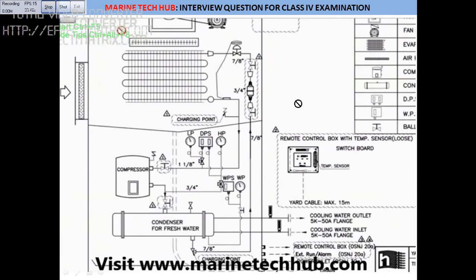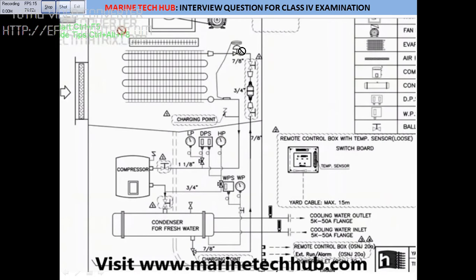In this schematic diagram, the components we have are: the condenser, which is cooled by fresh water — fresh water in and out. The liquid freon from here will go through a dryer with silica gel, which absorbs any moisture in the system. This dryer can be changed by closing the two valves — very important. Afterwards, the liquid will go through an expansion valve.